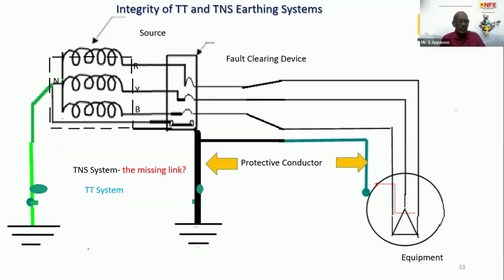If we make it act as the earth fault current path also, then the problem comes into the picture. If the link is removed, then it becomes a TT system. Here you have to make the fault current suffer this resistance as well as this resistance. Though you have provided a very low value of protective earthing conductor, it has to suffer 10 ohm here, another 10 ohm here. Totally, your fault protective device will not sense, will not act for the earth fault.